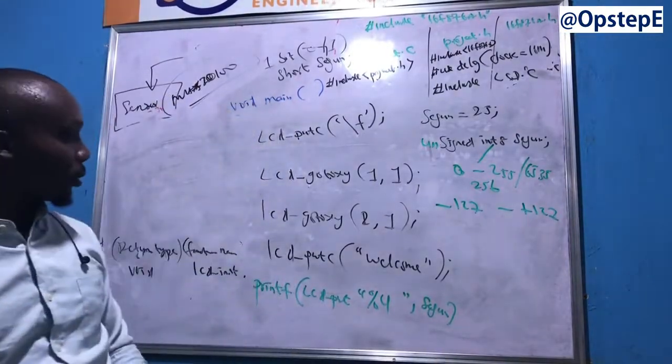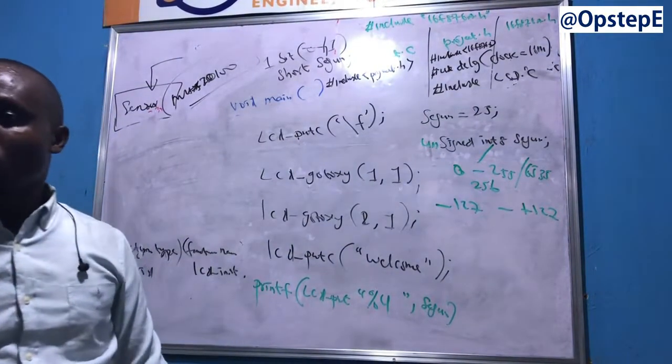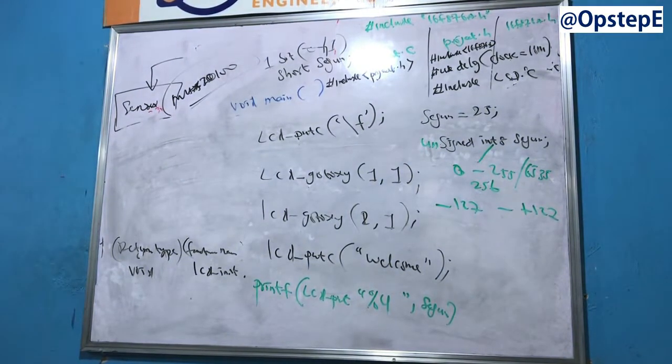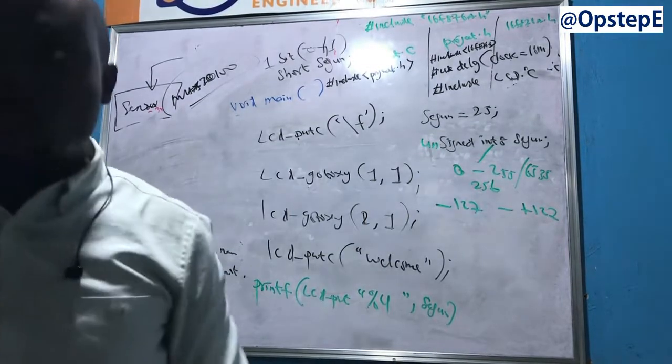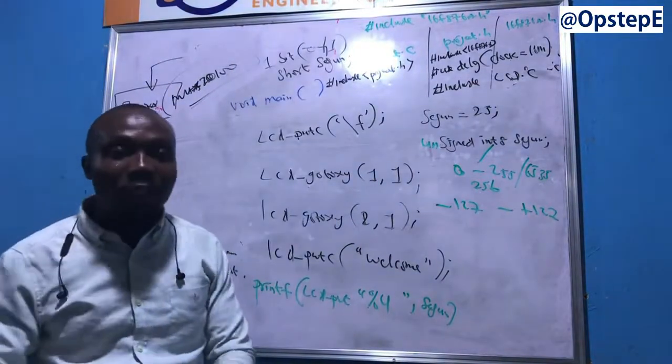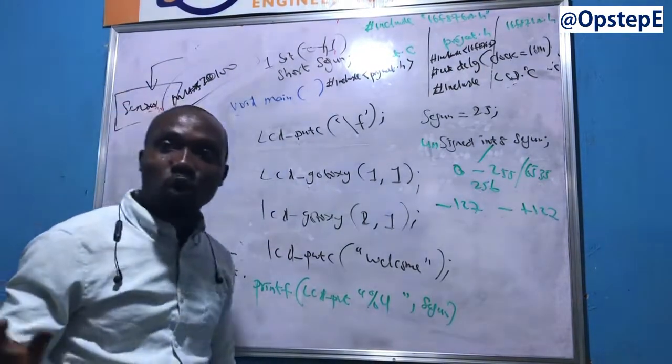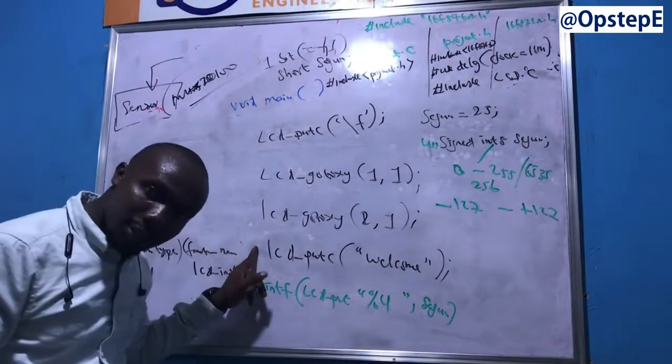That's what you're talking about. Is it for you to display? No, to display this number. Because this BPM is a register. This SPO2 is also a register. The content of the register is what is displaying here. So it displays the content, and don't forget that the content keeps changing. Because it is the content that it is showing, the value can keep on changing. But the part where it is displaying constant strings, unformatted strings, is why this BPM does not change, SPO2 does not change, this colon does not change, the percentage sign does not change, because they are what? They are constant information. So it's a mixture of both, this and this.